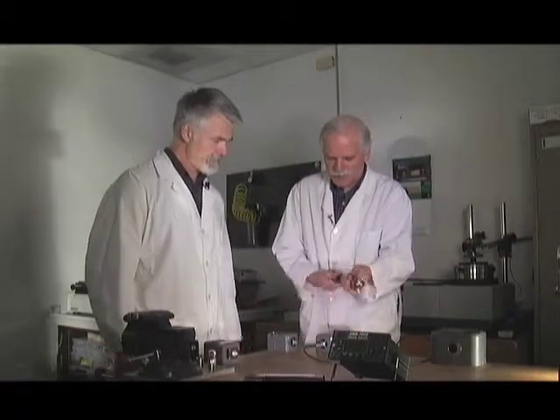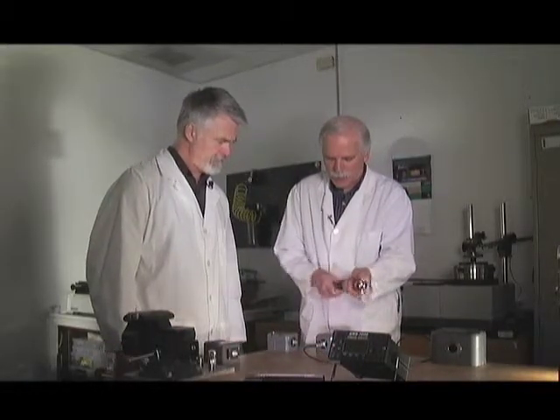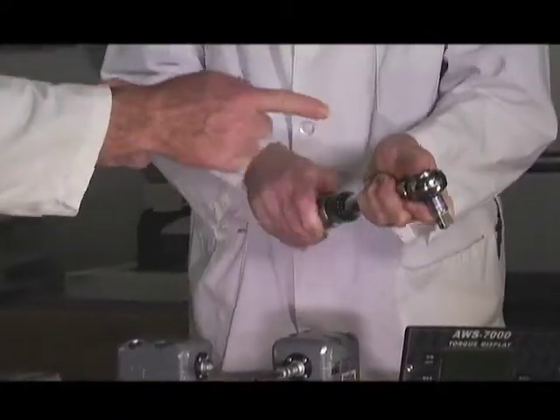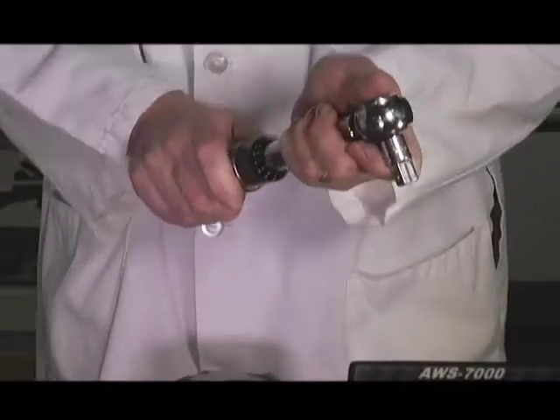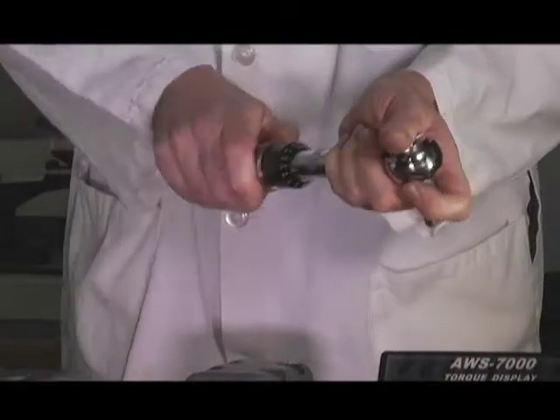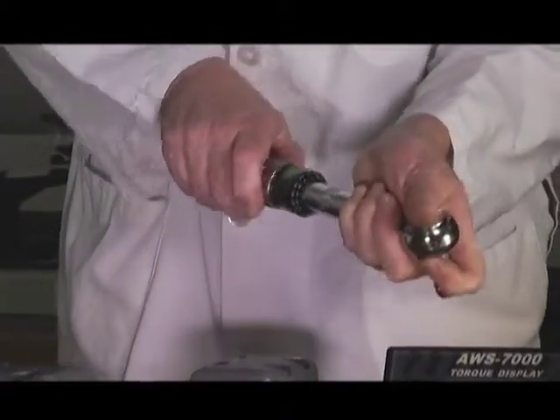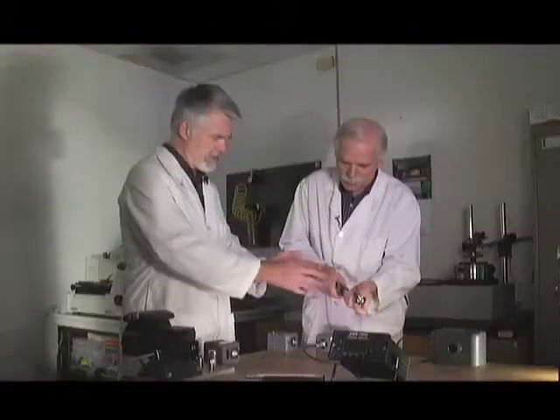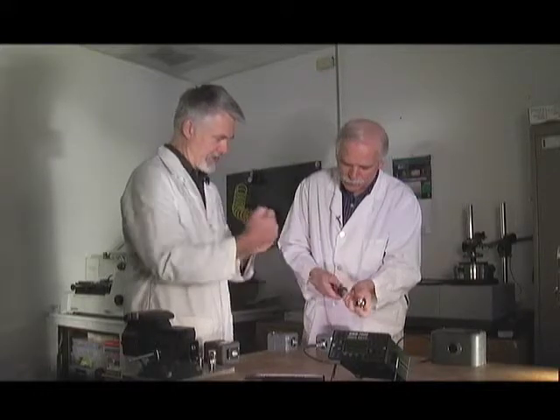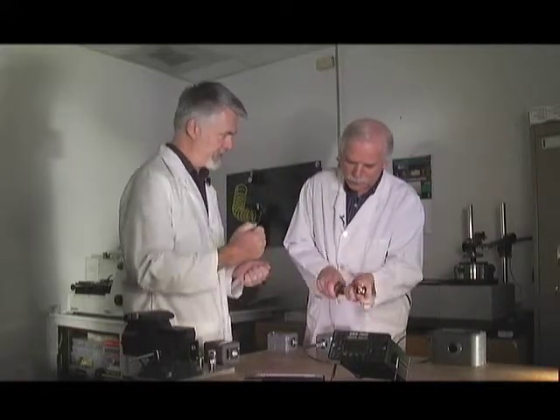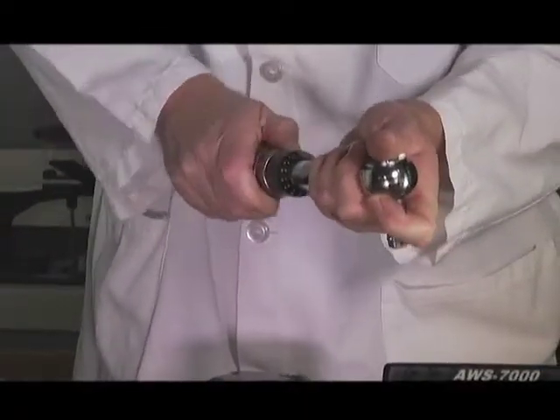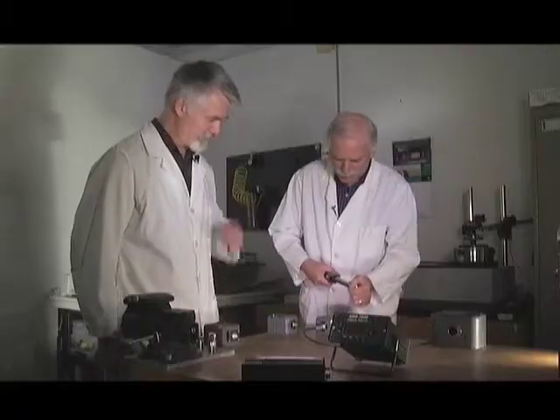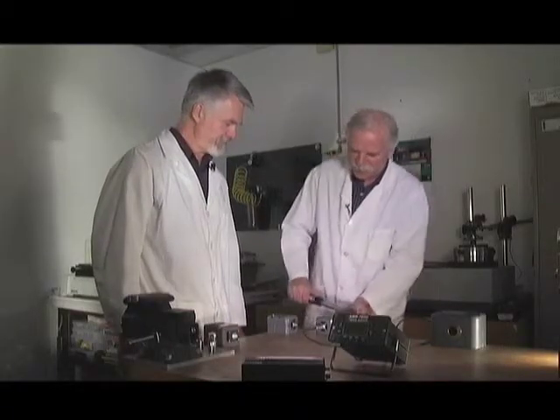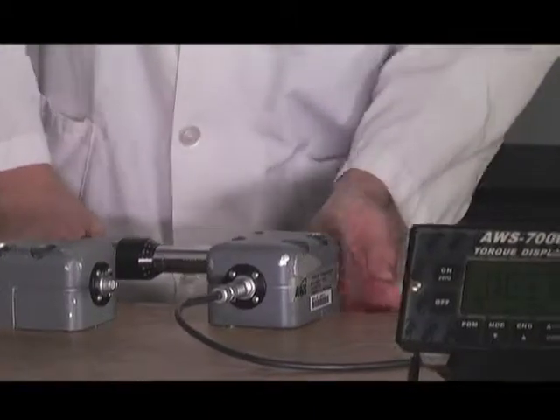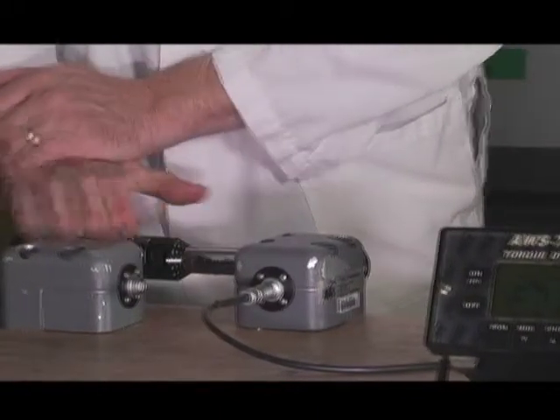Yes. I'm going to set this up to a higher range. Now, what's actually happening inside is you're compressing a spring, and that's a key factor to how these have to be cared for. The spring is actually pushing on something that makes it harder and harder to turn. There's a little breakover inside. Now we're set up to the 250 inch-pound, and we're going to give it a few pops.